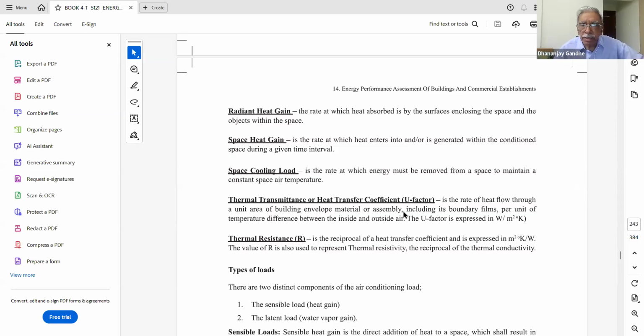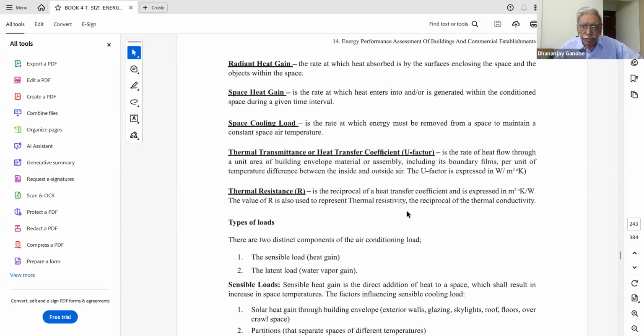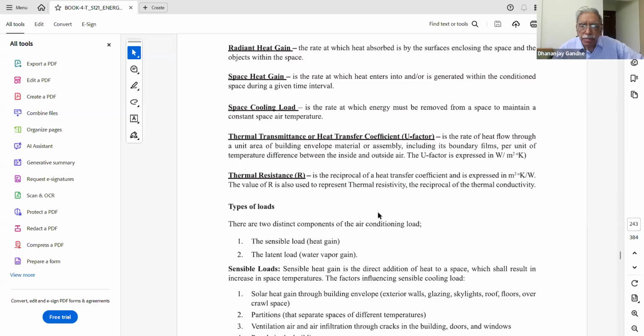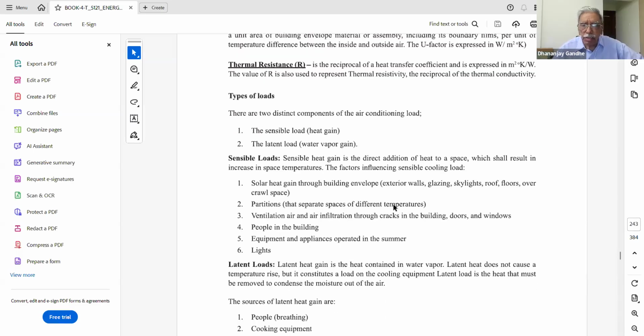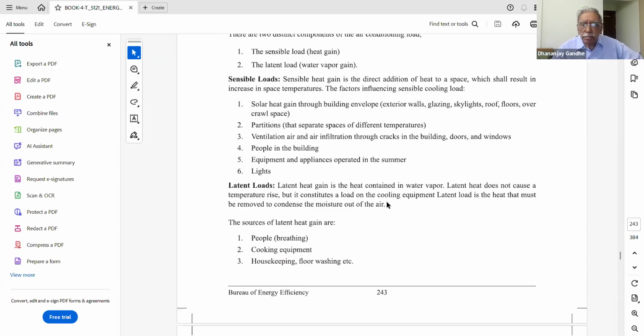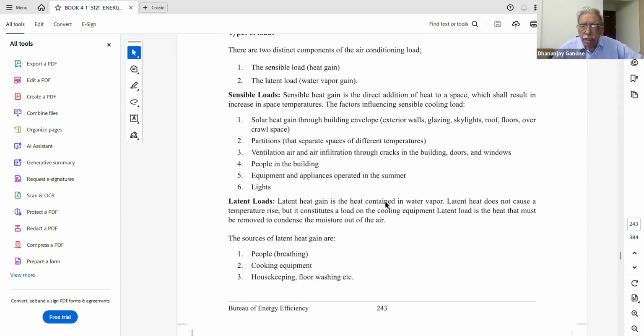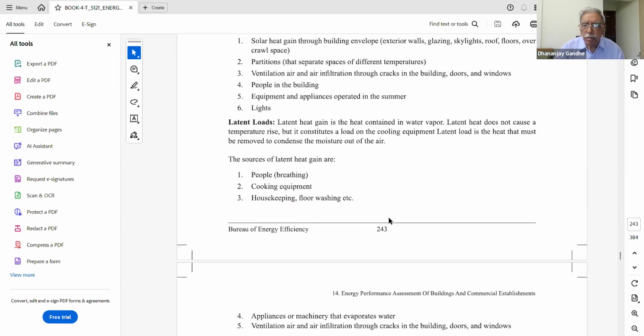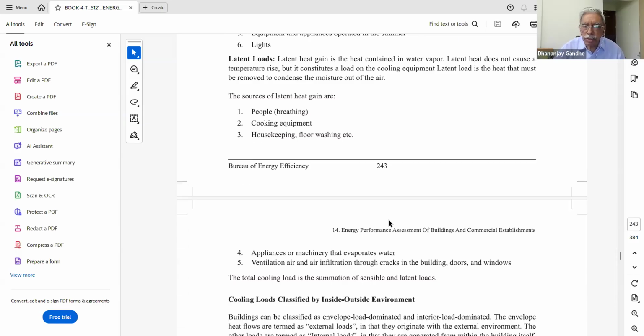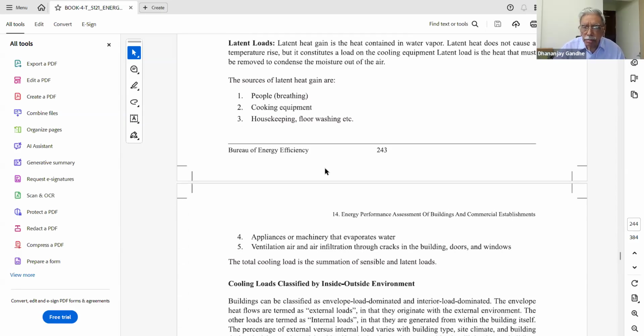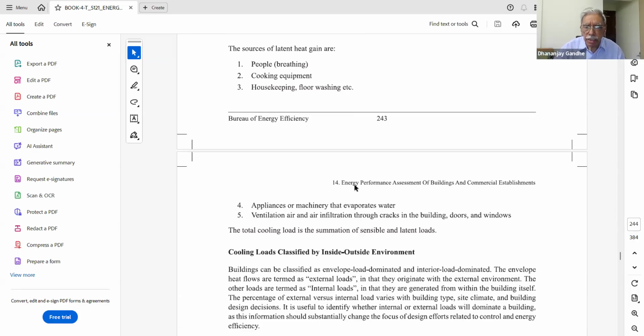Also the radiant heat gain, space heat gain, that we have seen. And there are two factors. What is it? The thermal transmittance factor, which we have to calculate, and the thermal resistance, we have to calculate. So we have understood what is sensible heat, sensible heat loads, which result in sensible heat imparted to the envelope. Also the latent heat, from which sources we get it. So what is the latent heat load? That also we have seen over here.